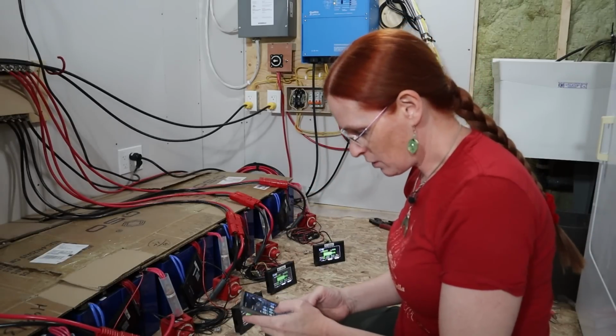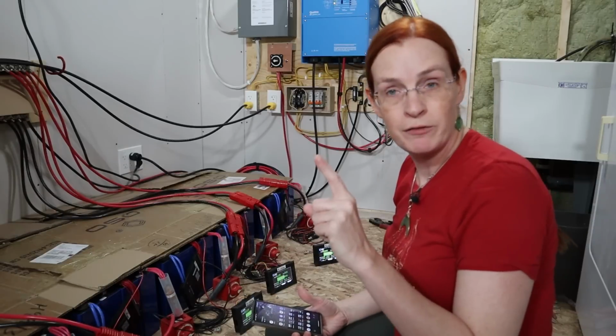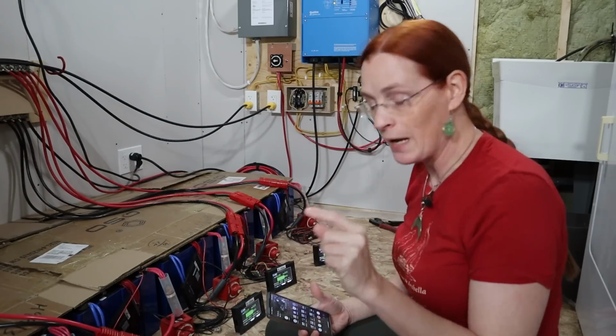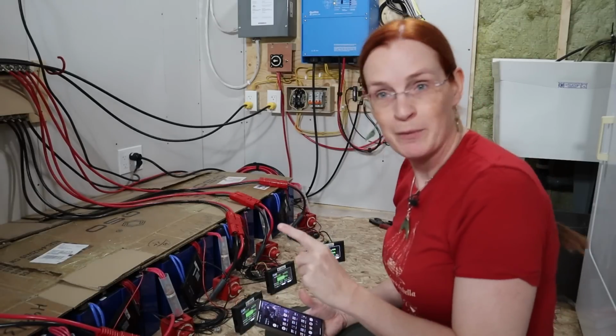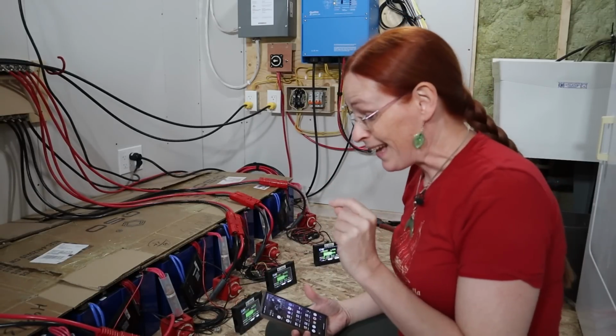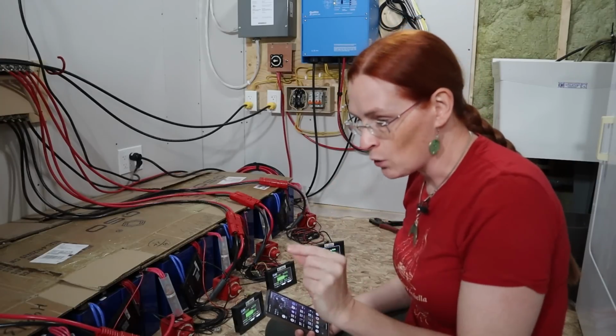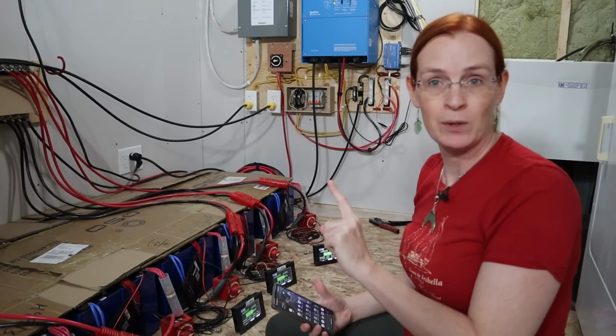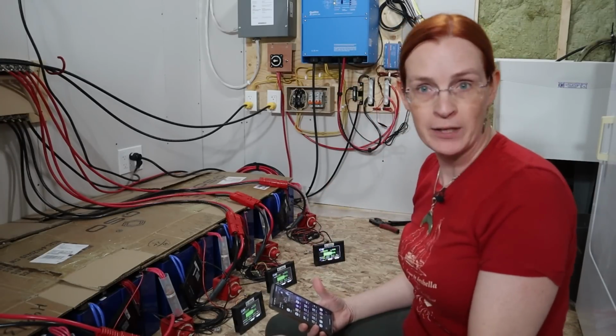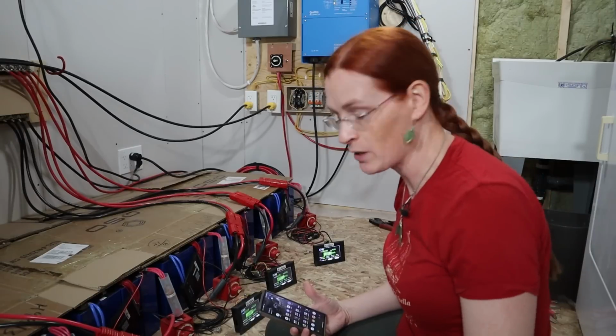With that, let me start a screen record. I am going to leave pack A at 3.0 as it's shipped by JK. I'm going to set battery B to 3.1. That's higher than the batteries are at most of their curve, so I expect that one to be very close to battery A, worst internal parasitic loads possible.